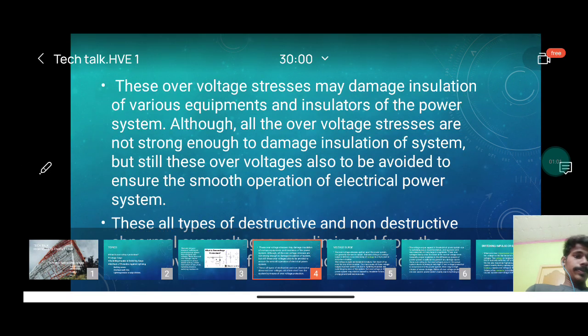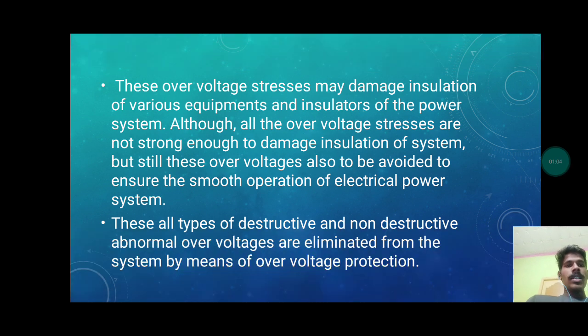Next, these over voltage stresses may damage insulation. Insulation damage means heavy voltages will come, and obviously this damages various equipment and insulators of the power systems. Not all over voltage stresses are strong enough to damage the insulation of systems, but these voltages still affect the smooth operation of the electrical power systems. Next point, all types of destructive and non-destructive abnormal voltages are eliminated from the systems by means of over voltage protection.